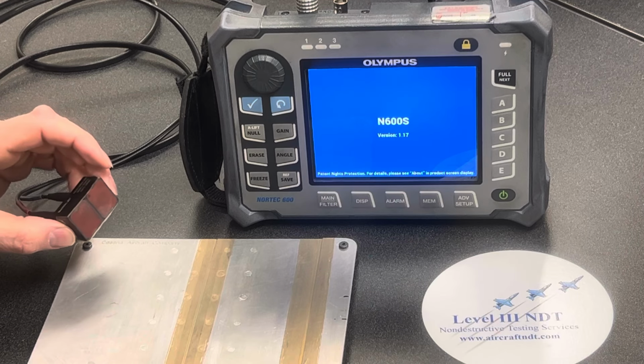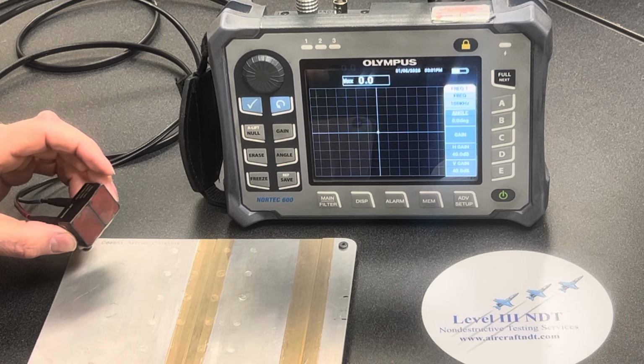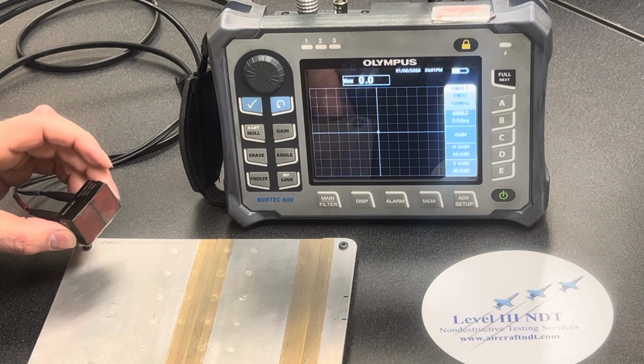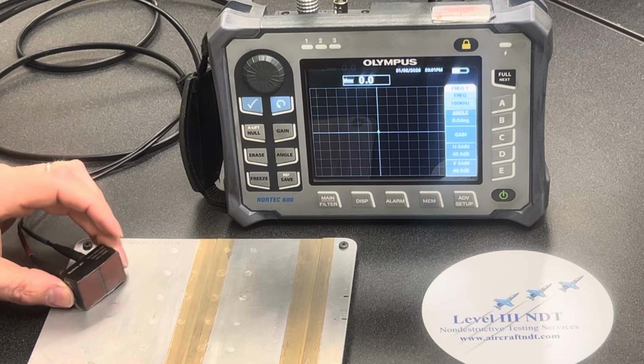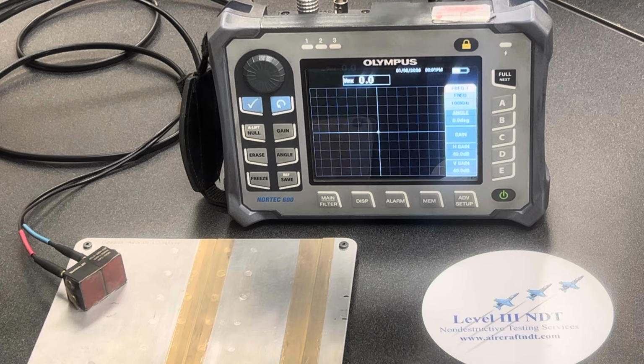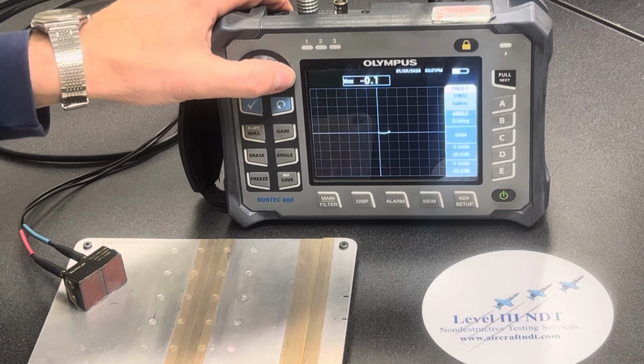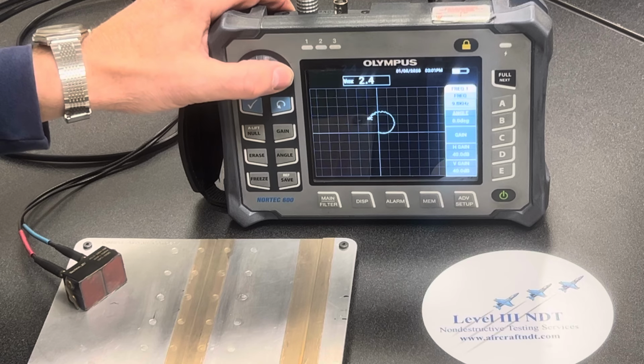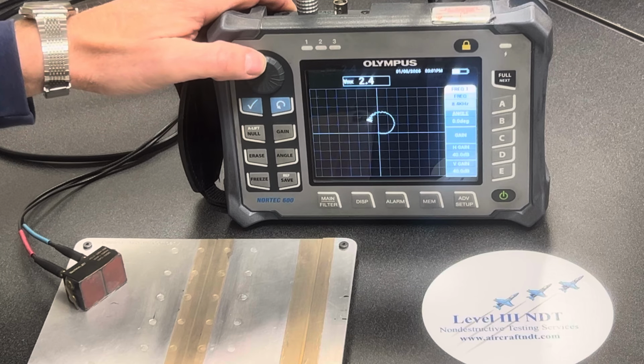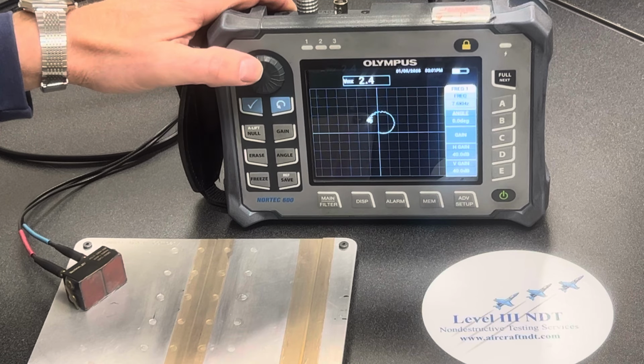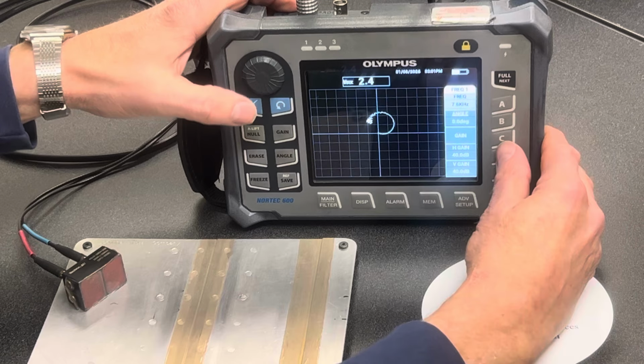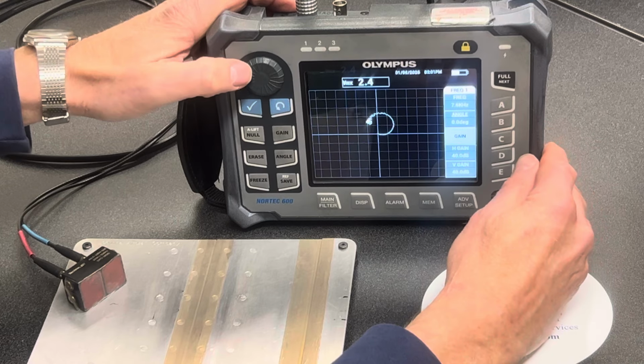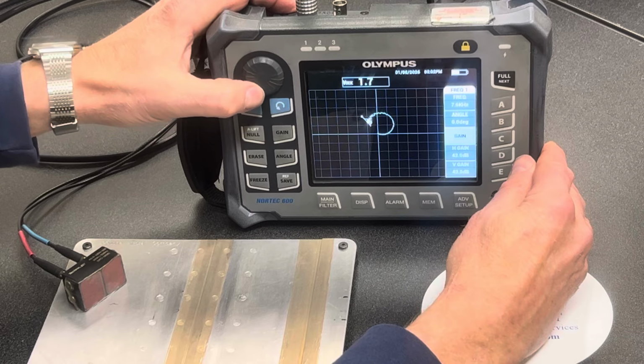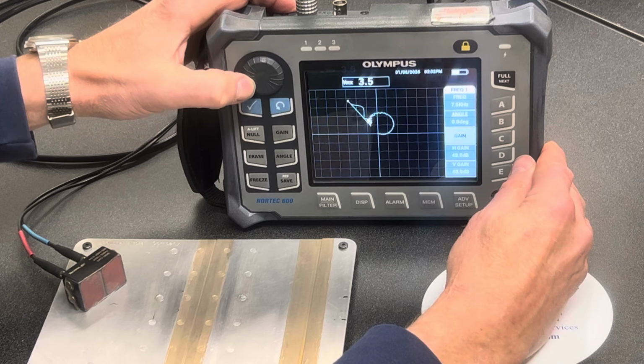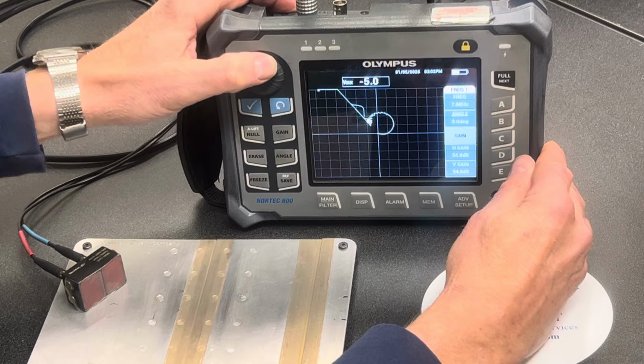We also have a layer of Teflon tape over both the inspection and calibration areas of the standard on the butt joint section and the skin seam section to simulate paint. The first thing we do is adjust the frequency from the default setting on the instrument of 100 kilohertz to what's specified in the non-destructive testing manual, which is 7.6 kilohertz. We'll also set our gains. We'll set the gains to go simultaneously to approximately 56 decibels.